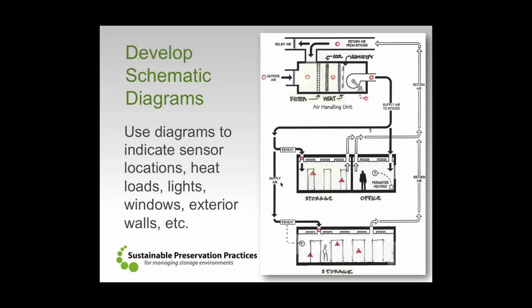And then moving into this overall diagram to just realize what that relationship is, sort of on a macro scale, as we start to look at the overall building, understanding, well, if we know where the mechanical system is and we know these red circles are where we place data loggers, this is where our data within the mechanical system is coming from. But we also go out to the spaces that get served by that mechanical system, and, well, here's a data logger that I have in the space, and here's another one. This room that's, maybe down the hall or next door, we've got a couple of data loggers in there as well. And as we start to get these diagrams going, we understand what those physical relationships are between the different spaces, but also the mechanical system that serves them.